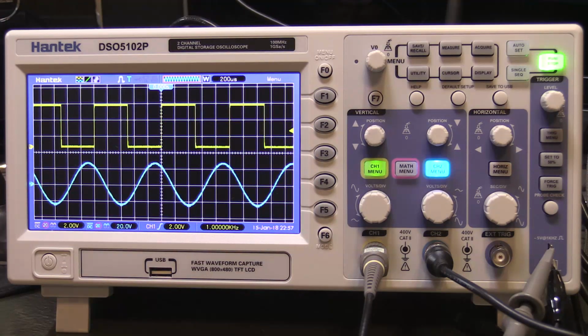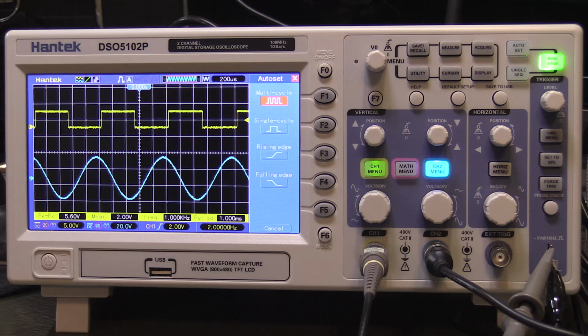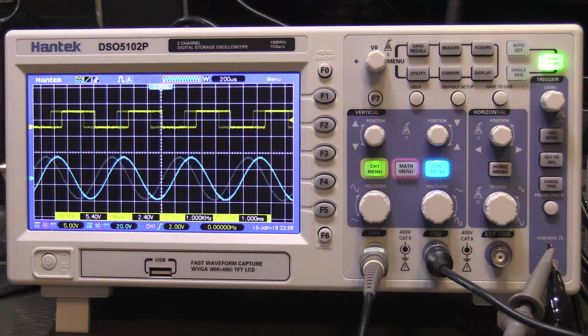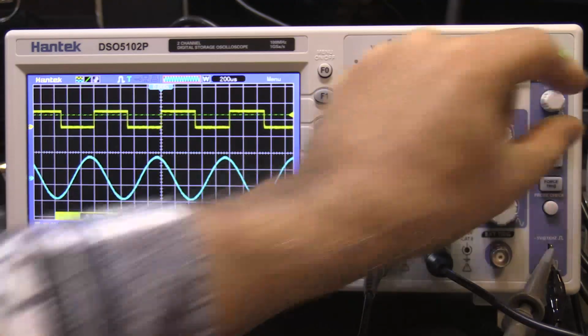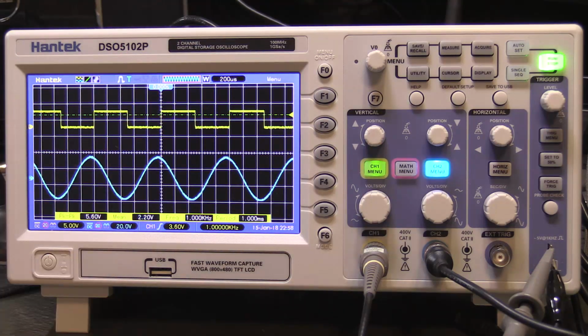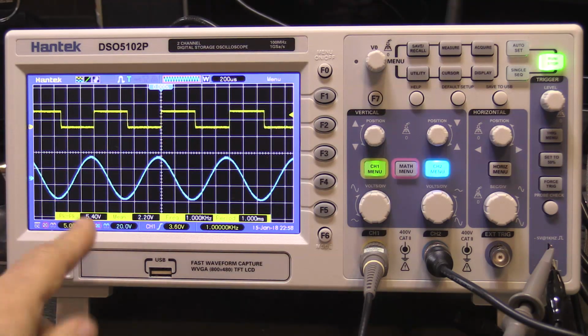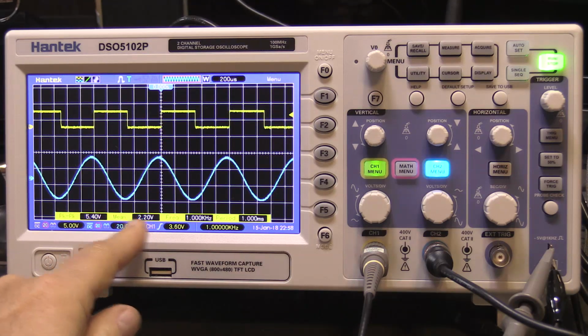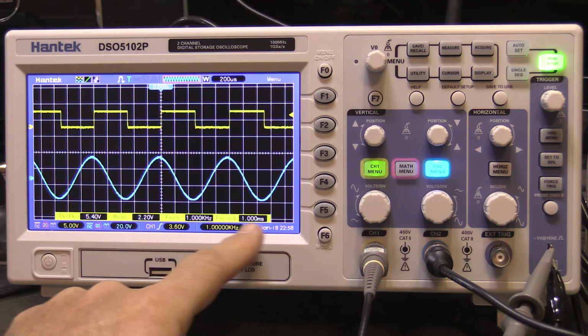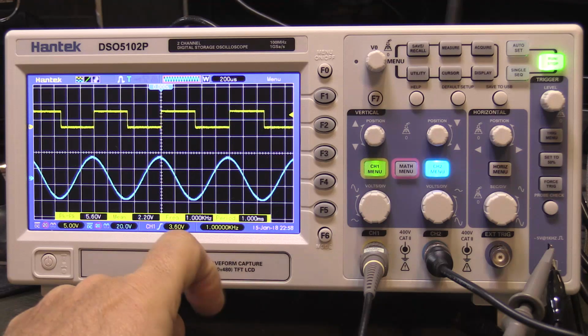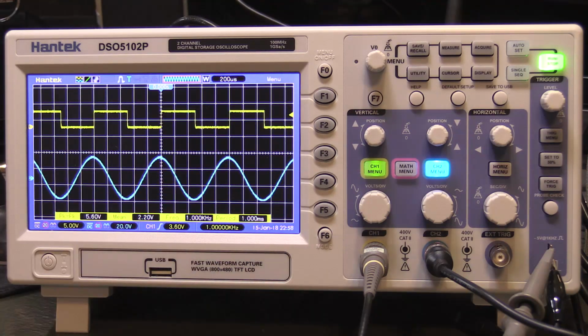So you're going to turn it on normally after you've done your initial calibrations and such. And what's really nice on a digital storage scope like this is you press auto set, and you'll hear some relays clicking, and whatever waveform you have coming into it, bam, it will go ahead and pretty much put it in the ballpark of where you want to be as far as the settings. So you can get it to a starting point that's really sort of good to go with, and it'll give you your basic readouts here, your peak to peak, your mean voltage, your frequency, your milliseconds time period here, wavelength versus frequency. So you can choose how much of this stuff to have on the screen as well.